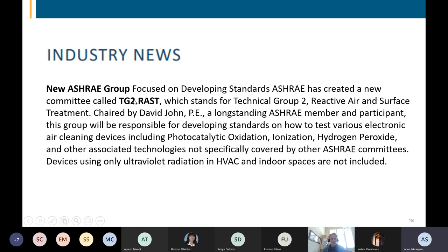ASHRAE has formed a new TG, which is a technical group 2 for reactive air cleaning system technologies. It has just been implemented and put in place. And in fact, they had their first meeting at the last ASHRAE AHR in Las Vegas, I believe. It is a TG group, technical group right now. It is taking on membership that it will be tasked with providing standards and testing protocols and procedures for all advanced, what I would call reactive air cleaning system technologies, including bipolar ionization, needlepoint bipolar ionization, dry hydrogen peroxide, photocatalytic oxidation, and others.